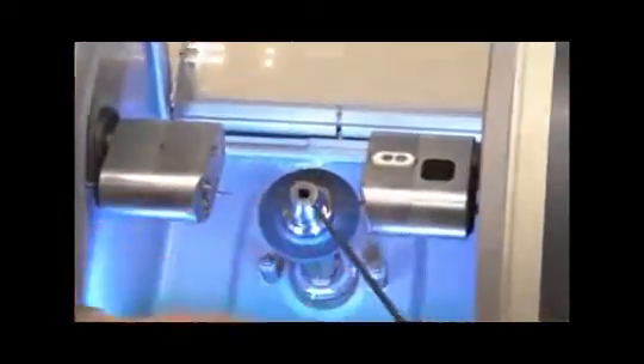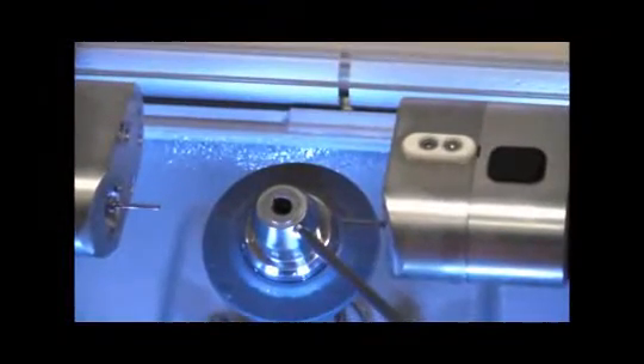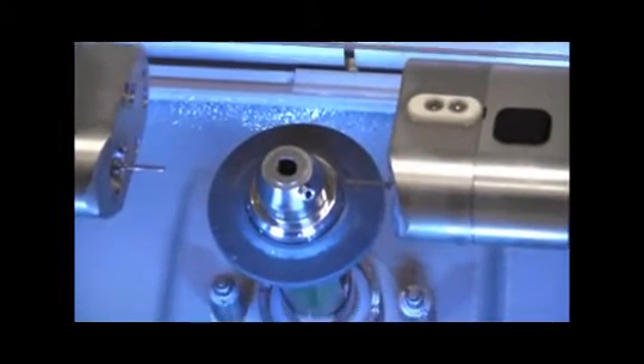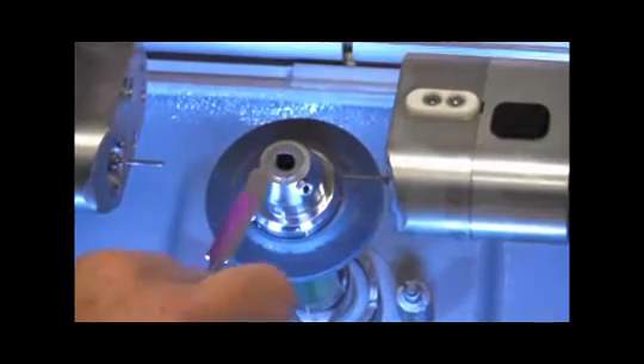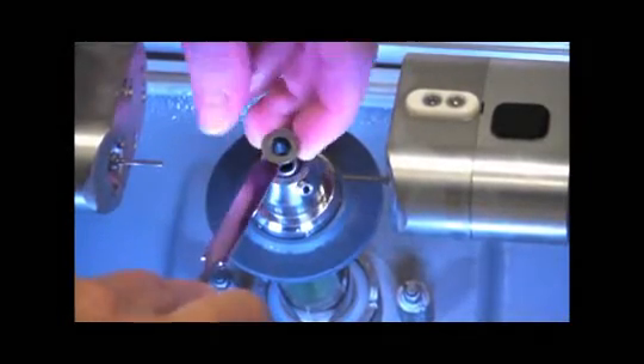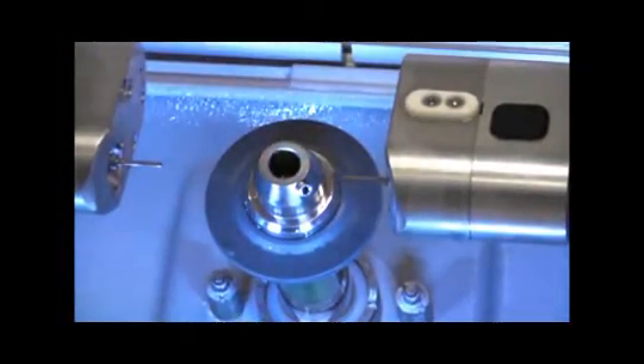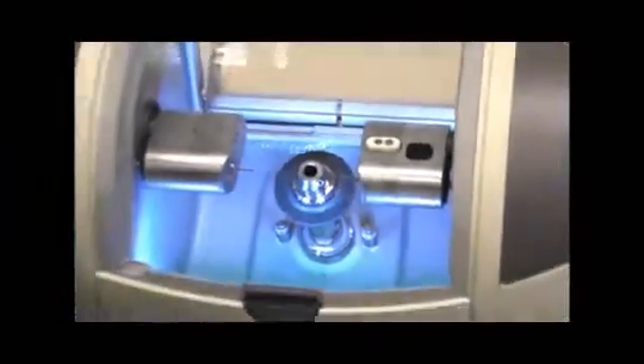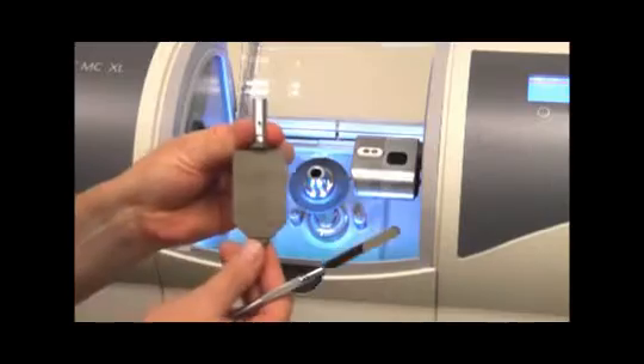Use the provided torque screwdriver to loosen the screw on the block chuck to remove the centerpiece. You can use a flat-headed screwdriver or a mixing spatula to remove the chuck. Now input the calibration specimen.